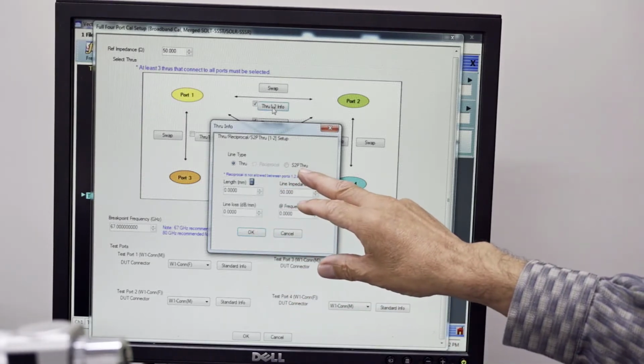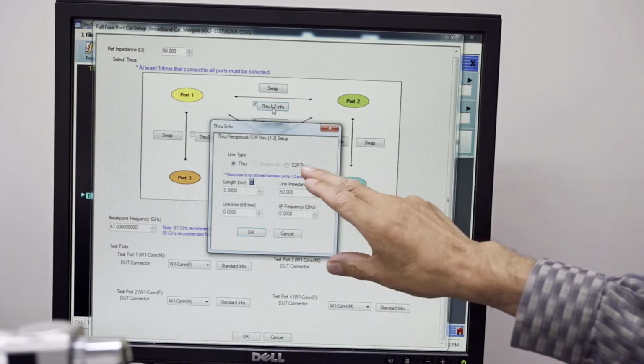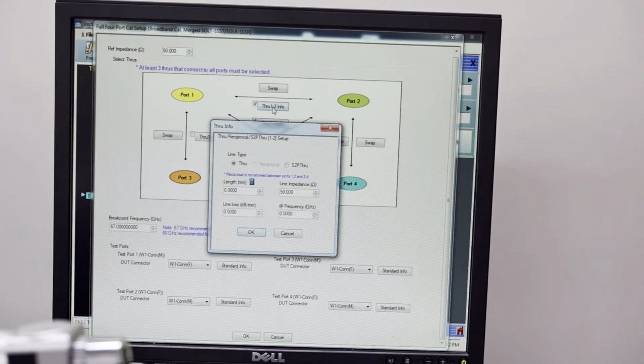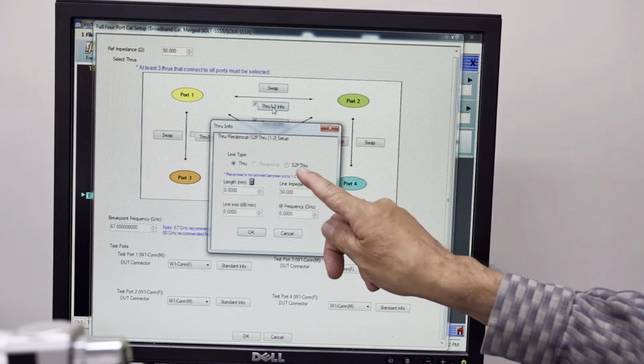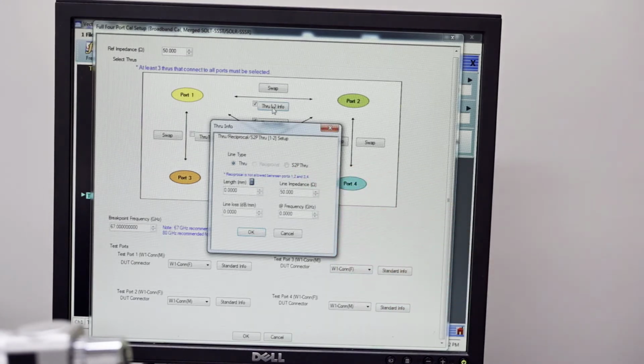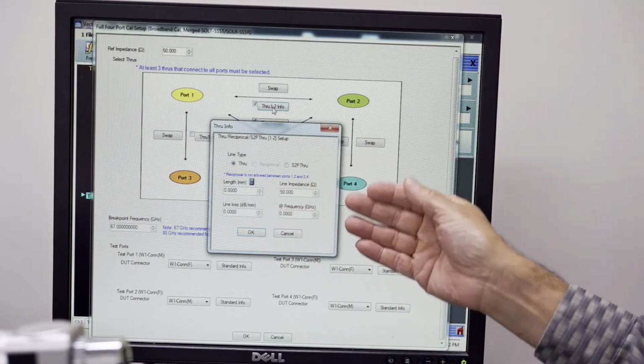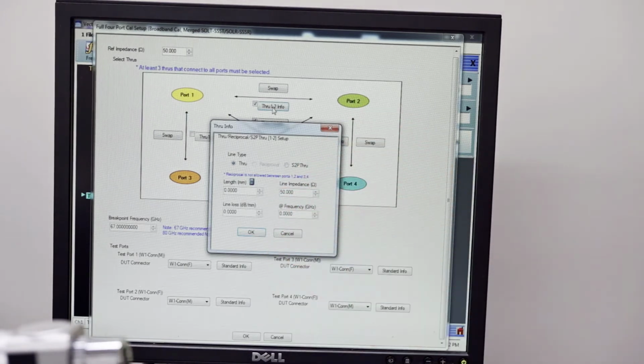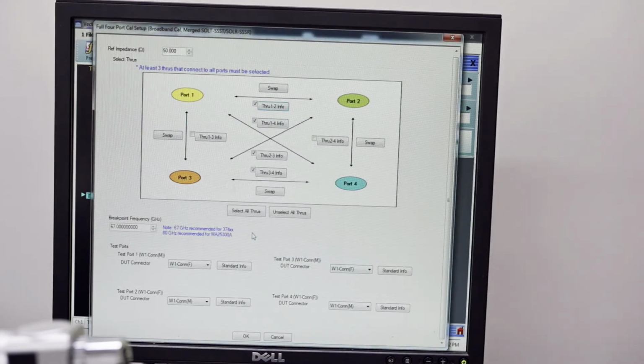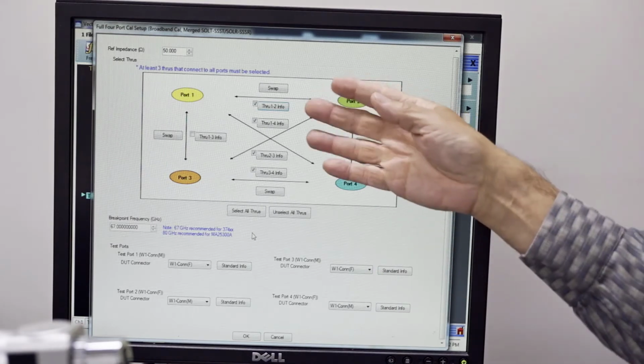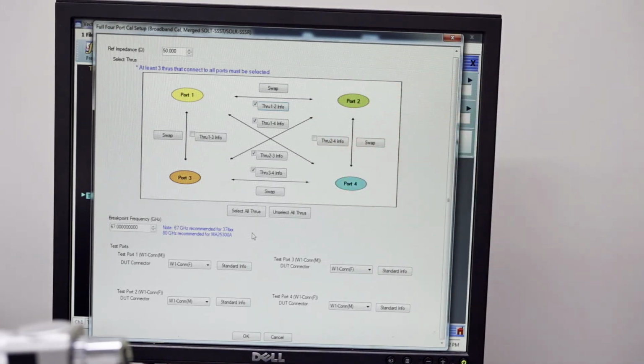Also, if you have an S2P file available for the through, you can designate the S2P file. And that's very useful for these kind of situations where you need to do de-embedding. And so if you have a test fixture that you have an S2P file, then you can select the S2P file for your fixture, and that will give you an added boost in performance during the calibration. So you see there's plenty of options here to configure your throughs and define your throughs. And in this case, we just enter the 0 and select OK. And you go through each of the throughs that you've selected and define them that way.